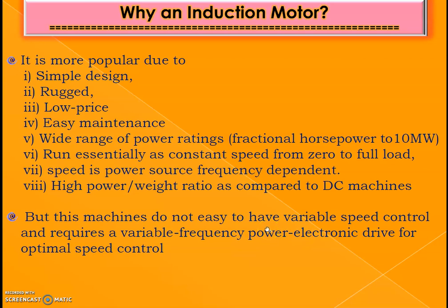The major disadvantage is that this machine does not easily have variable speed control. It requires variable frequency power, because speed depends on frequency. To adjust the frequency we require a variable frequency supply, which is possible only through power electronic devices. This is the only disadvantage of the induction motor; otherwise all advantages are good, and many people prefer it especially for constant speed operations.